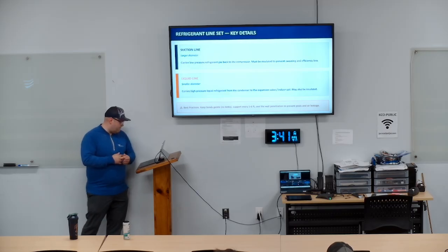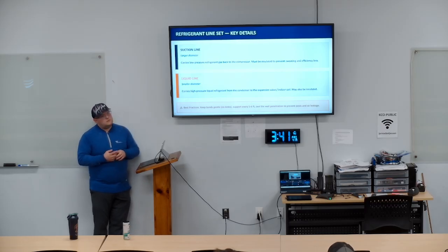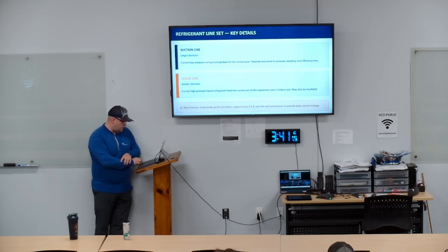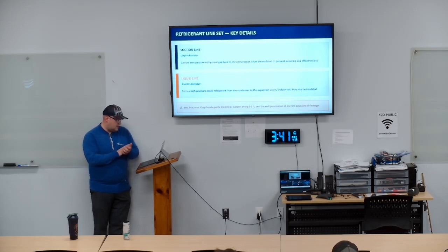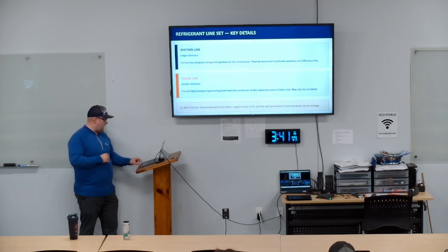So know that. Liquid line, smaller diameter, goes to the expansion valve from the condenser and then into the evaporator coil. Best practices. Keep the bends gentle when we're bending. Sometimes you got to take a hard bend and then just people being around it, hitting stuff, ends up folding. And then we're screwed. We got to cut it out, redo what we just did. So, yeah.